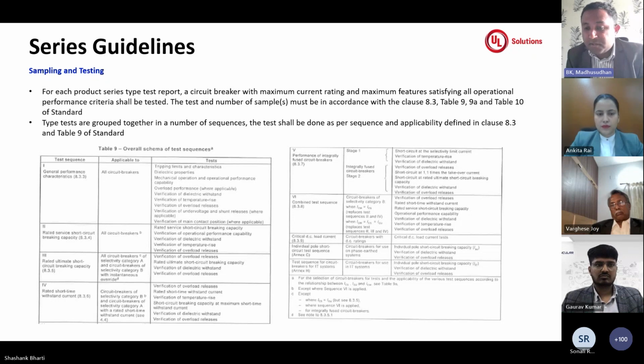For sequence 2, you can use separate samples. The standard allows this because there are certain critical tests, especially short circuit and electrical endurance, where after the test for long service, the breaker may not be used again. So to know the design and the criteria coming from the product, sequences can be done on different samples, and the criteria have to be met based on the end result from the particular testing. Next slide, please.